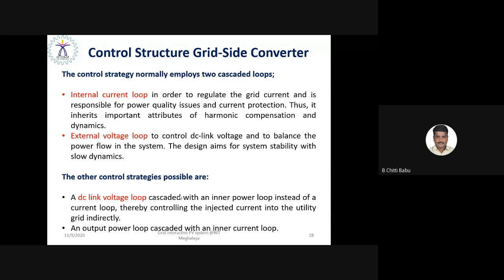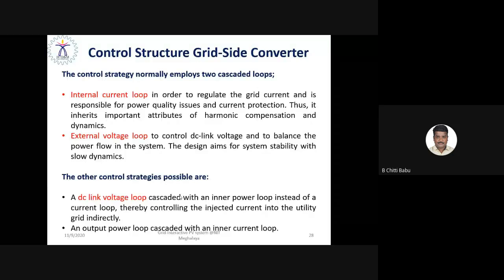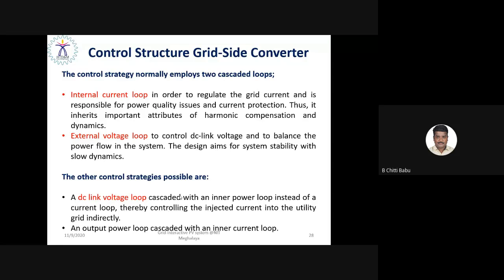So further, the control is necessary to shape your grid current waveform as sinusoidal. That must be harmonic free. That is possible with the help of the internal current controller. Moreover, it has to be designed with a large bandwidth so that it can provide an excellent transient or dynamic response.